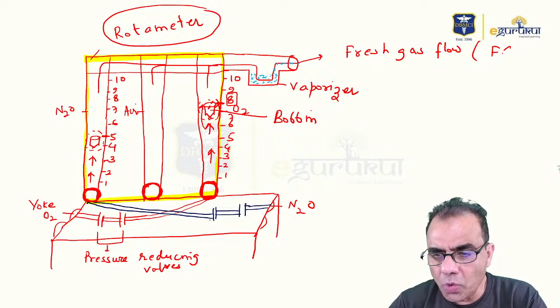Fresh gas flow is the final mixture which is coming out of the anesthesia machine, and it comes out at a pressure of 5 to 8 psi. Imagine, if it is an oxygen cylinder, what was the pressure? 2000 psi. And what the patient is getting is just 5 to 8 psi. So now you can imagine how drastically these pressure reducing valves are reducing the pressures.